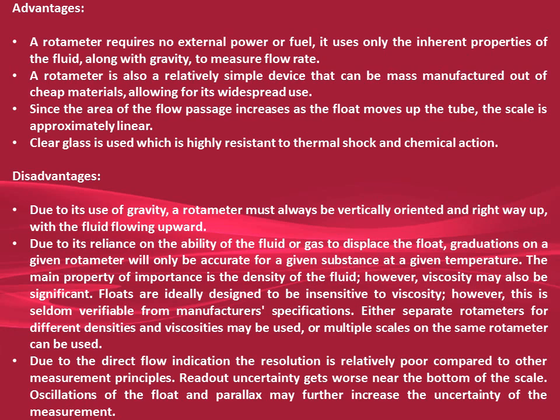The main property of importance is the density of the fluid; however, viscosity may also be significant. Floats are ideally designed to be insensitive to viscosity; however, this is seldom verifiable from manufacturers' specifications.